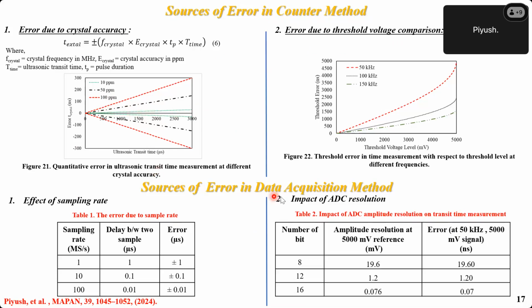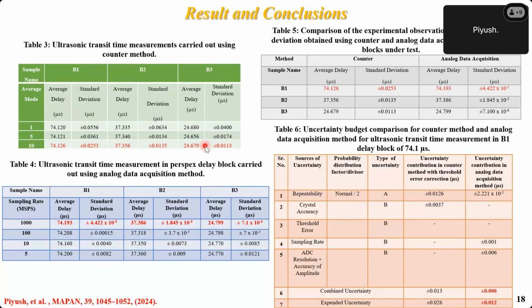The data acquisition method also has two errors, due to the sampling rate and due to the ADC resolution. Here we can see that we require a high sampling rate to minimize our error. At 1 mega sample, we get an error of plus or minus 1 microsecond, which is very large. The ADC resolution does not affect our measurement much, so we can set it at 8 bit. Now we measure the ultrasonic pulse velocity with both instruments in different averaging modes. Here we can see that by increasing the averaging, we get a lower standard deviation in the measurement. And by increasing the sampling rate in the data acquisition method, we also get a lower standard deviation.